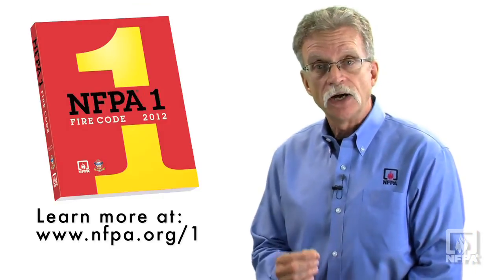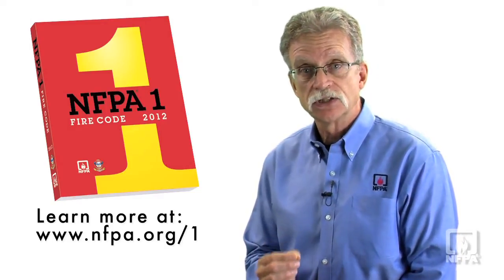Secondly, NFPA 1, the National Fire Code, in Chapter 11.12 gives very definite guidance on the installation practices for the panels. It addresses things like access paths for the fire department. In a residential structure, it recommends a minimum three-foot setback from the edge, from the eave, and from the ridge for the panels, and that there be several pathways — a minimum of three feet wide — going from the eave to the ridge of the structure to allow the fire department access to the roof for ventilation and other firefighting operations. For larger structures, it also provides recommendations, increasing the setback distance and the width of the egress path for the fire department.